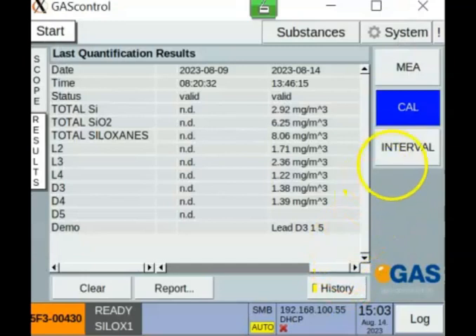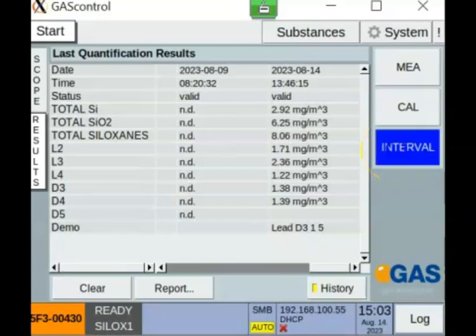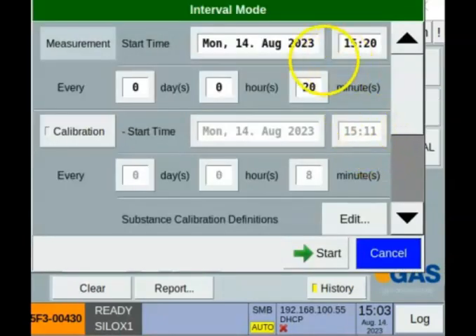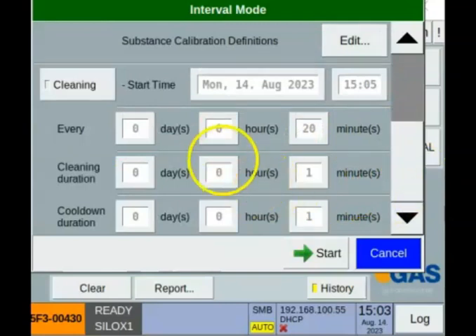Another possibility is to run the instrument in a continuous monitoring mode, the interval mode. It is possible to select the starting time of the interval, the frequency of the interval, and it is possible that once in a week or at another frequency you can activate a one-point calibration. And last but not least, after a certain time of measurement, you can send the instrument to the cleaning mode.